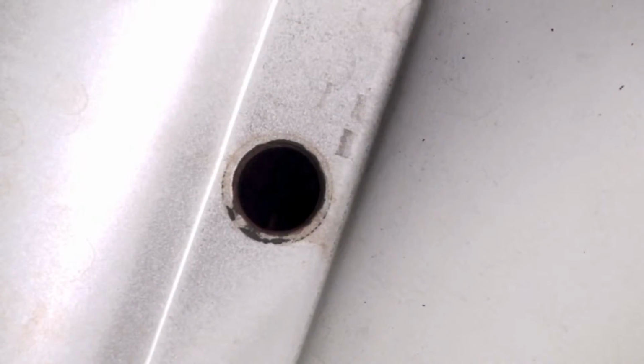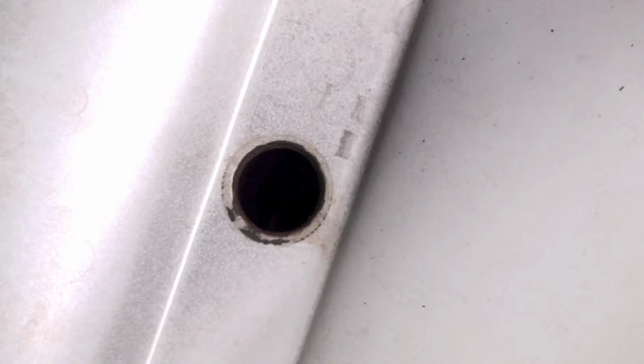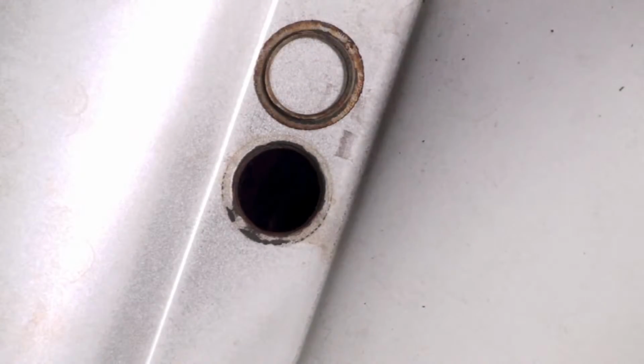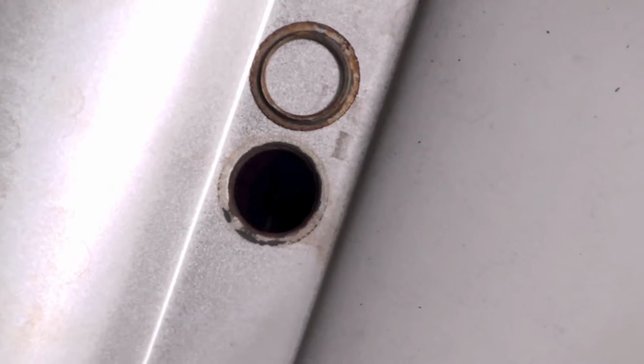If you look closely, you'll see on this one the ring's missing. Now here's the ring. They pop off and they drop down. Most of the time they drop into the blower. Sometimes they'll drop onto a blower shelf and you'll find them there. But they pop off. Now let's look at the rest of this heat exchanger.